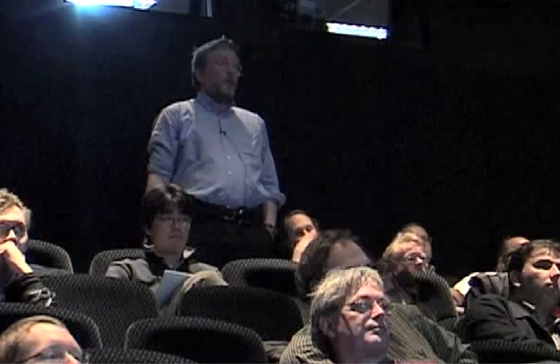So, what's wrong with it? There you have got a decimal point and an up arrow on the same button. The up arrow button changes mode, the decimal point's obviously a decimal point. And various modes it's got there. International regulations say clinicians should not write micrograms using the Greek mu, because a Greek mu can be misread as an M, and a microgram and a milligram differ by 1,000, so this is a good way of causing errors.